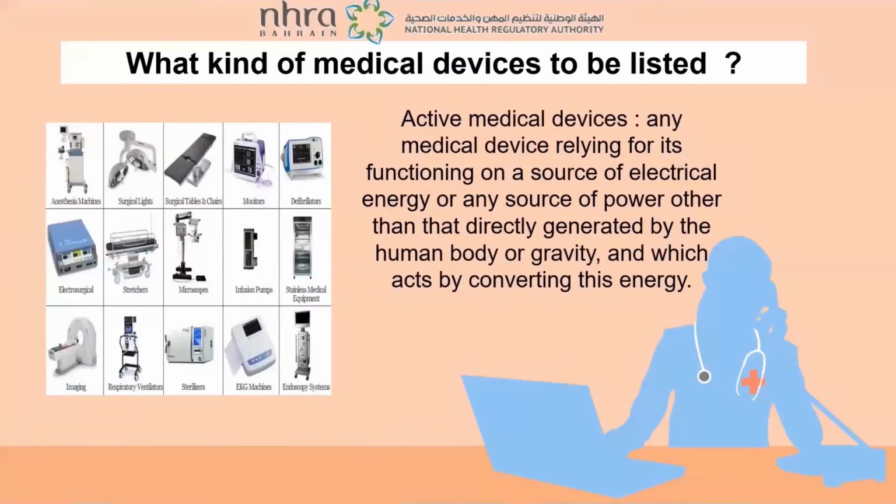Okay, so what kind of medical devices should be listed? Active medical devices, which means any medical device relying for its function on a source of electrical energy or any source of power, other than that directly generated by the human body or gravity. So let's say a medical device doesn't use the source of energy or batteries or anything. So these kind of medical devices shouldn't be listed on the list.